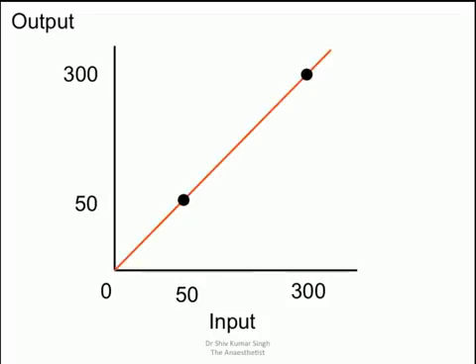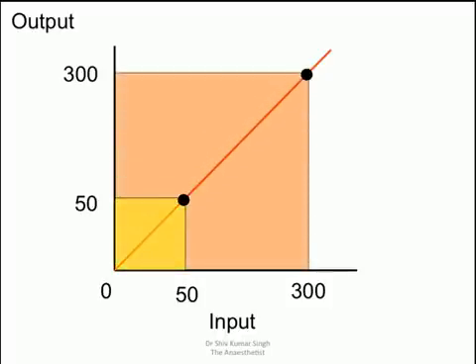So we look at it graphically. This is the points you get. So the two points. The 0 is 0. At 50 it shows 50. At 300 it shows 300. So this is a well calibrated machine. But you could actually get points which could be at low range. So they have a lower slope drift, or a higher slope drift.